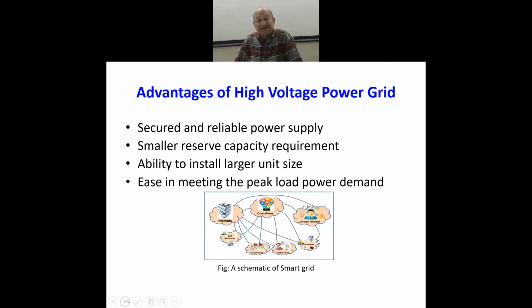Under that condition, it would be advisable to start generation of power through different sources under the peak load conditions. And there we take help from the hydroelectric power plants, because the hydroelectric plants take only 3 to 4 minutes, when we open the gates, to start running the turbine and synchronize it to the grid. That takes such a short time, unlike the thermal power stations, which take hours and hours, 10 to 12 hours minimum, because you have to have the rated temperature of the steam, superheated steam, etc. And that takes a very long time.